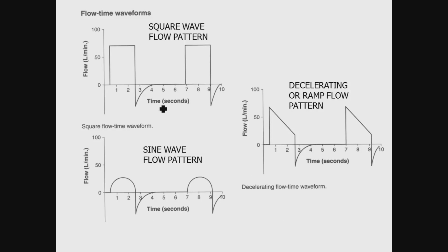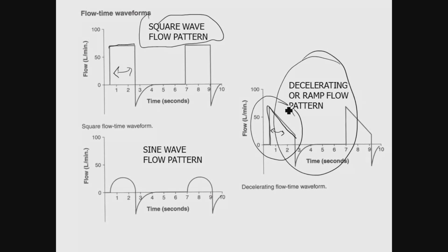Those flow patterns that we can set can either be a square wave flow pattern, where the inspiratory flow is fixed, or a decelerating ramp. In both cases, I'm determining the inspiratory time. Yes, it does matter, because it'll alter how that gas is being delivered. Typically, I will tell you in assist control, volume control, we're using this pattern. And we'll talk more about that later.